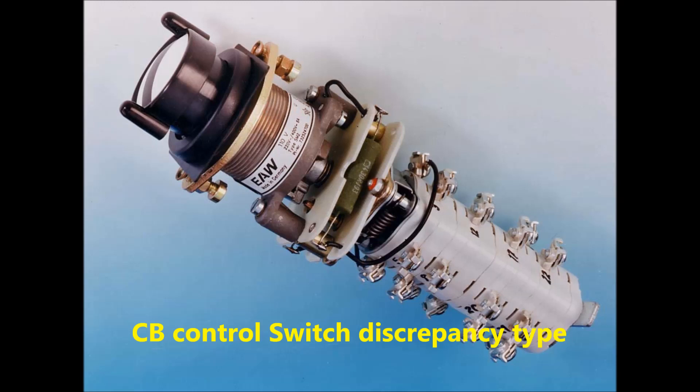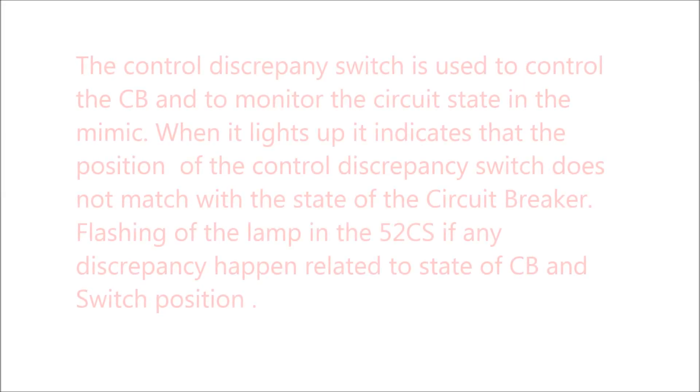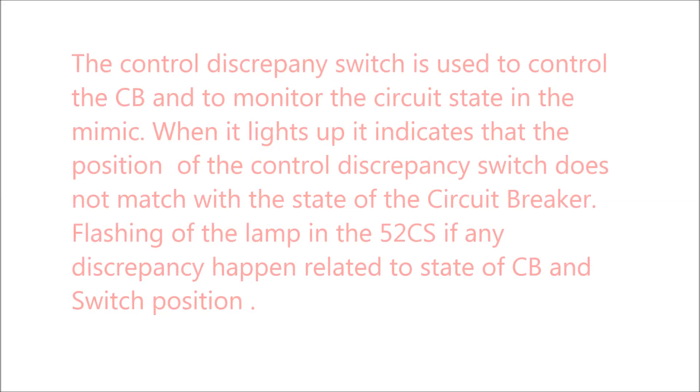The 90 degree rotary control switch is used for acknowledgement signaling switch, and the 45 degree press and twist switch is used to control the circuit breaker. The control discrepancy switch is used to control the CB and to monitor the circuit state in the mimic.